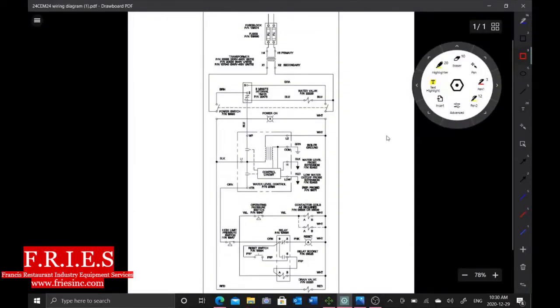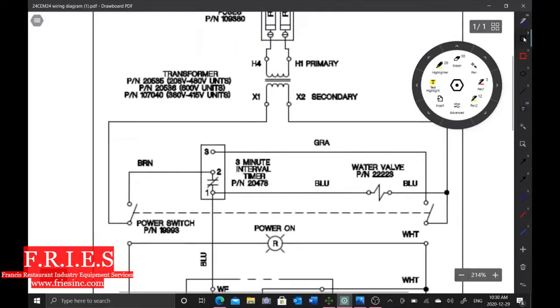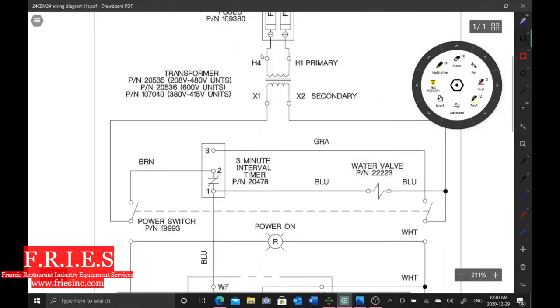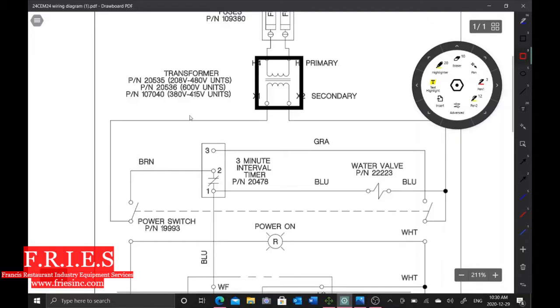So here's our schematic. Our transformer that keeps blowing is this guy right here. So what I've done is I've installed two fuses in line, one here and one here. And what that's going to do is whatever's shorting out our transformer, it's going to take out either side of these fuses, and then we save this very expensive transformer.